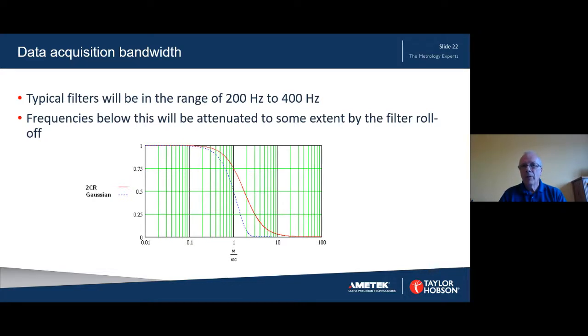The cutoff frequency is a very useful parameter for characterizing filters but it doesn't tell us the full story of how the filter is going to affect any particular frequency. This is because filters have a roll-off characteristic. Two common roll-off characteristics, the 2CR filter and Gaussian filter, are shown here. As you can see, for both filters the roll-off is significant down to about one tenth of the cutoff frequency.